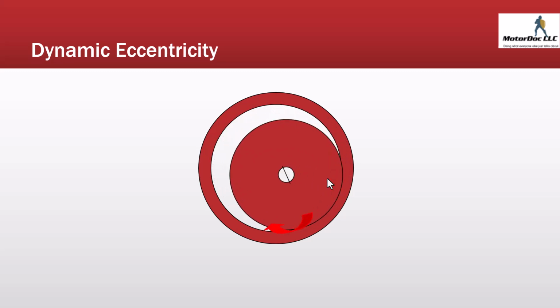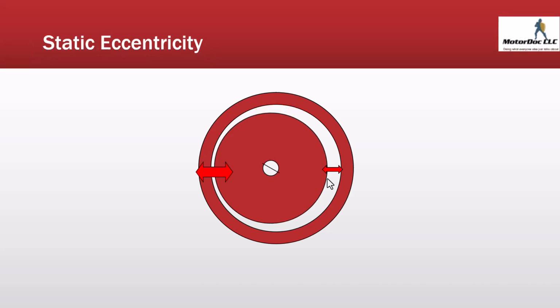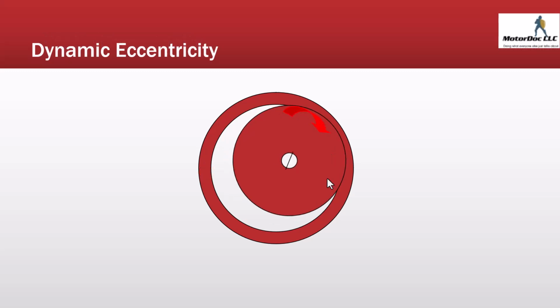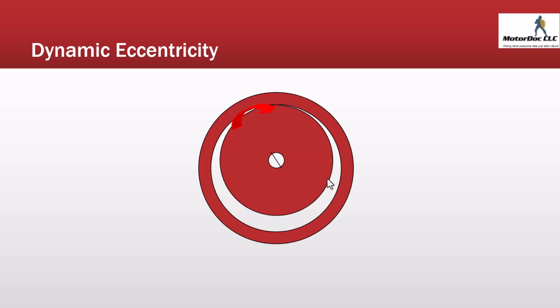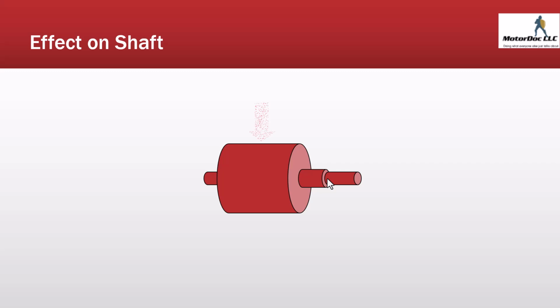Now, if it orbits in there, whether that is perfectly stationary and magnetically orbiting or physically, say a bent shaft, things like that, this could be from the rotor being off center, or if it's a belted application too much belt tension, or if I have soft foot, the rotor gets pulled off. This tends to occur if I have a lot of broken rotor bars, something going on in the rotor circuit, if it's a wound rotor, or a bent shaft, other conditions. Now I can have a combination of both. The other thing is if I have unbalance, torsional issues, misalignment, and any damage to the rotor, I'll also see those conditions. So I'm seeing a whole lot of stuff requiring us to be able to separate out the frequencies associated with that.